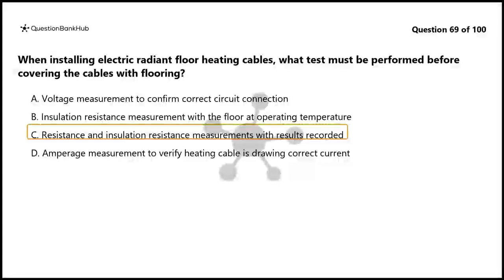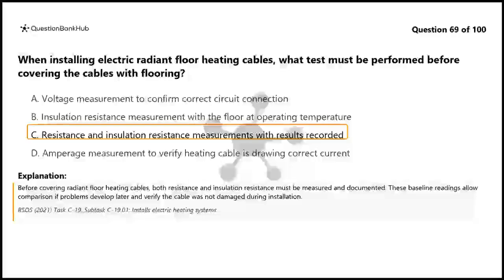The correct answer is C. Resistance and insulation resistance measurements with results recorded. Before covering radiant floor heating cables, both resistance and insulation resistance must be measured and documented. These baseline readings allow comparison if problems develop later and verify the cable was not damaged during installation.